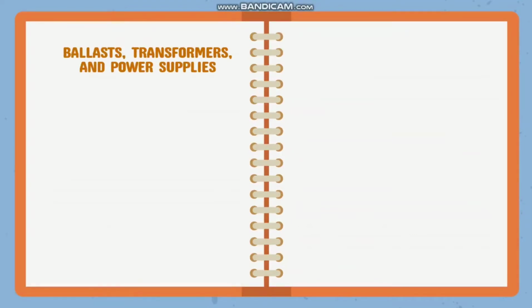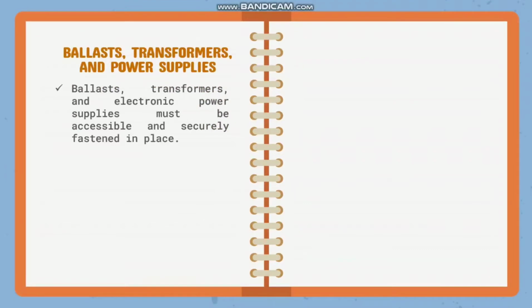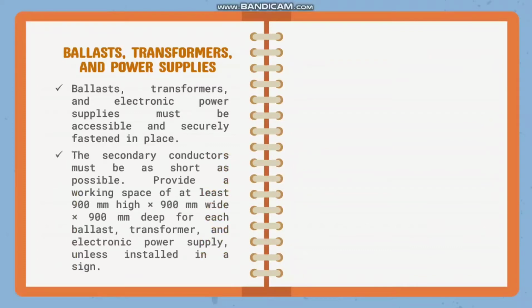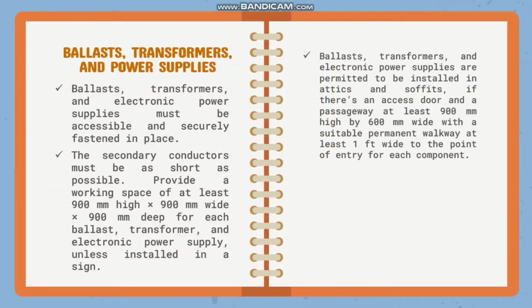For ballast transformers and power supplies. Ballast transformers and electronic power supplies must be accessible and securely fastened in place. The secondary conductors must be as short as possible. Provide a working space of at least 900 mm high by 900 mm wide by 900 mm deep for each ballast, transformer, and electronic power supply, unless installed in a sign. Ballast transformers and electronic power supplies are permitted to be installed in attics and soffits if there's an access door and a passage at least 900 mm high by 600 mm wide with a suitable permanent walkway at least 1 foot wide to the point of entry for each component.